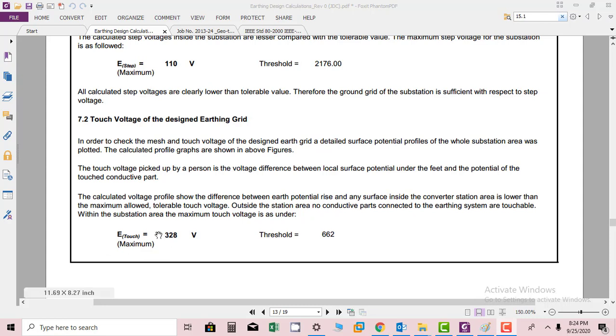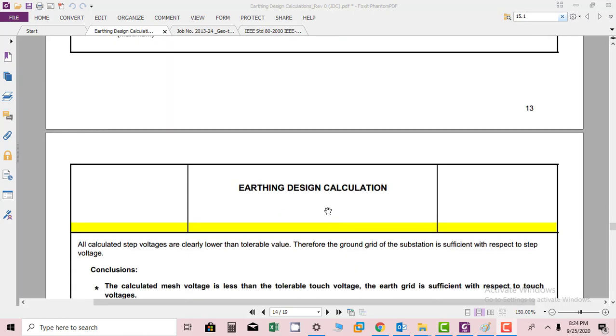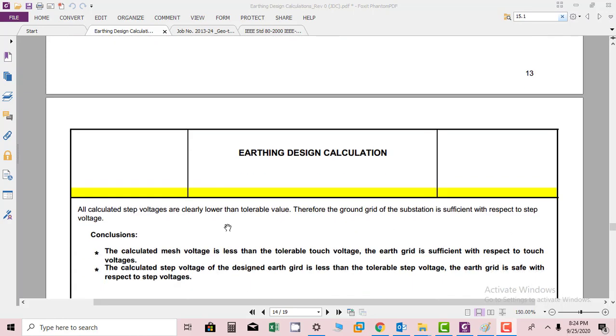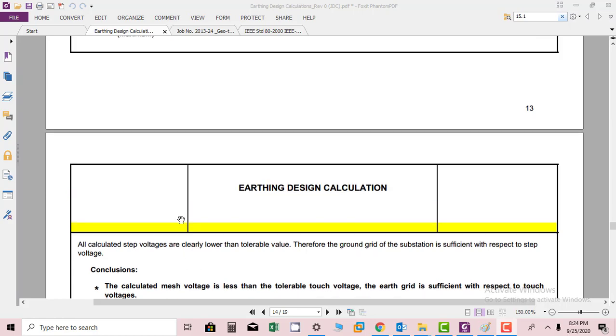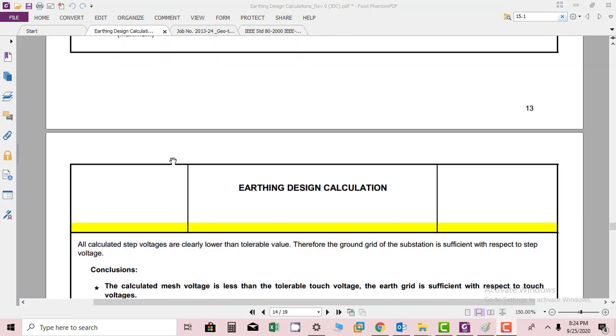The maximum touch potential is 328 volts as calculated, whereas the threshold should be less than 662 volts as per IEEE Standard 80-2000. This proves that the calculated touch potential for the substation is 328 volts, whereas the permissible limit is 662 volts, which is well below the limit.